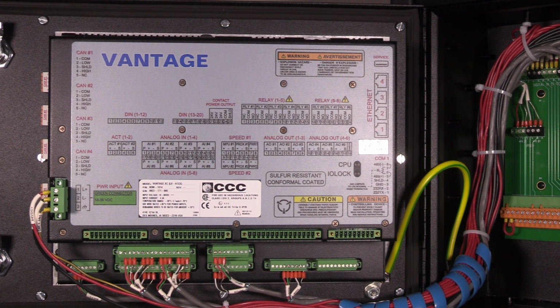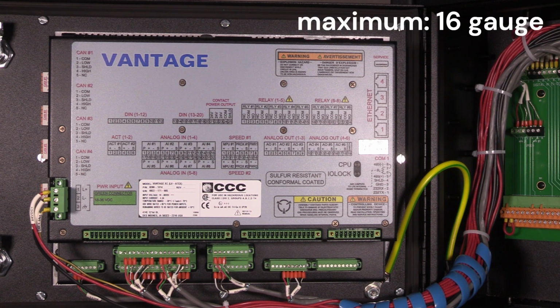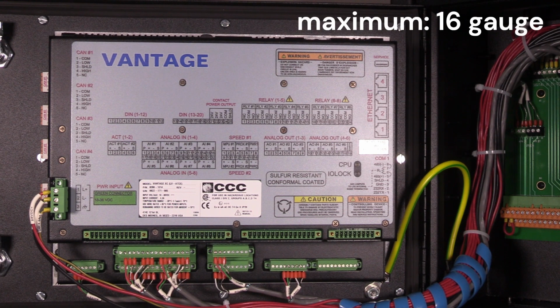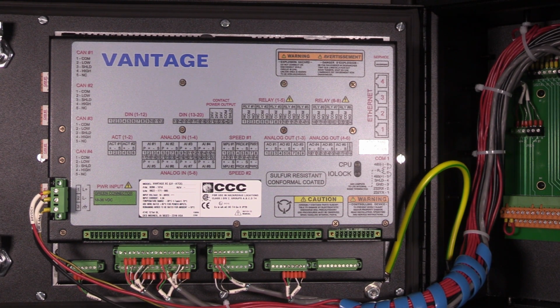All wiring in this section will be wired to the terminal blocks of the controller. You should remove the terminal blocks from the controller before connecting wires to them. The terminal blocks will accept a maximum wire size of 16 gauge. Each wire should have a 1/4 inch of insulation removed to create a connection without exposing too much wire. Please note that the order in which you connect the wires does not matter.